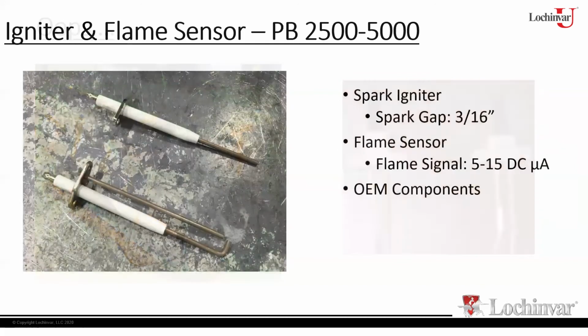Now for the larger models, 2.5 to 5 million, here we're going to a spark system. So here we have a spark igniter as well as a separate flame rod to prove the flame signal back. And again, we're going to look at that flame signal on the display. Same characteristics. I need at least 1 microamp to prove the flame, but typically 8 to 12 is where we're going to be.